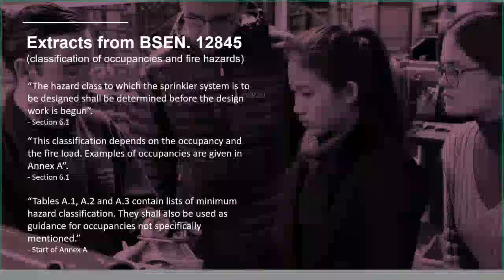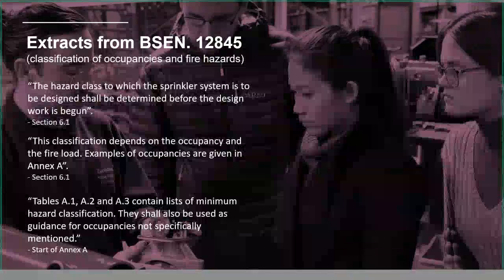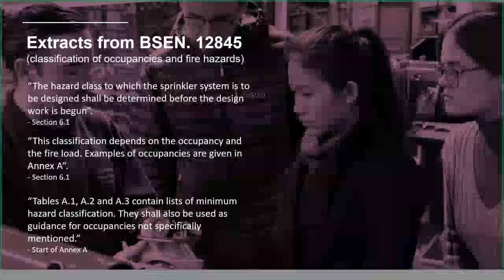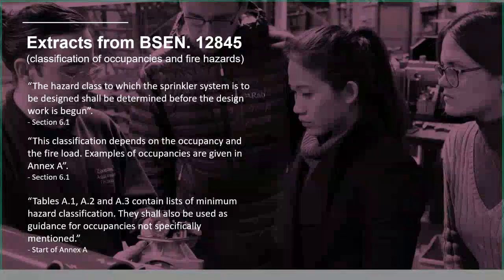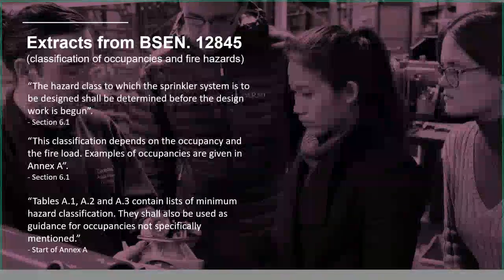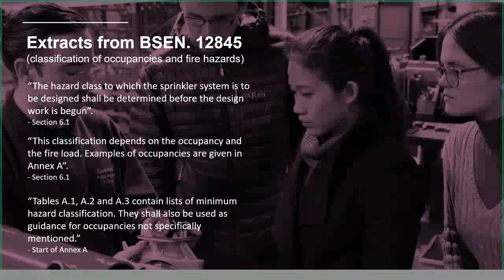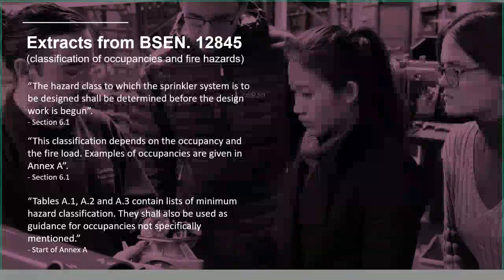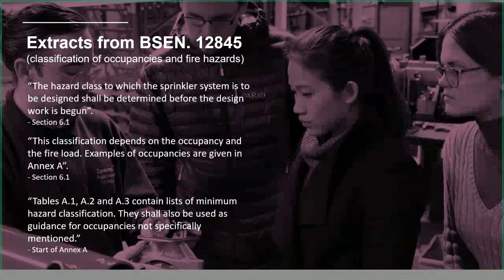At the other end of the scale, a prison has very low fire load — everything is metal and concrete with very little to catch fire, perhaps outside of the laundry room. Occupancy also matters: a large warehouse might have high fire load but only five people inside. Or you have a care home with vulnerable residents who have wheelchairs, Zimmer frames, and walking sticks — they take longer to evacuate, so occupancy plays a significant role.